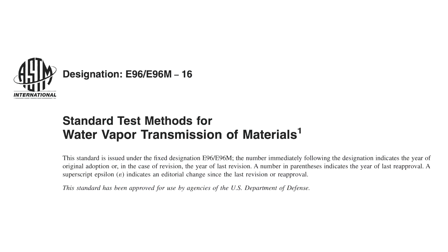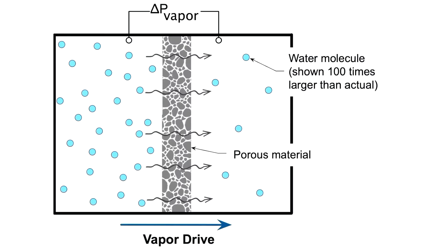This is what vapor permeance testing like ASTM E96, the most common type in North America for building materials, is focused on. Water vapor diffusion occurs when there's more water vapor on one side of a layer of material or an assembly than on the other.